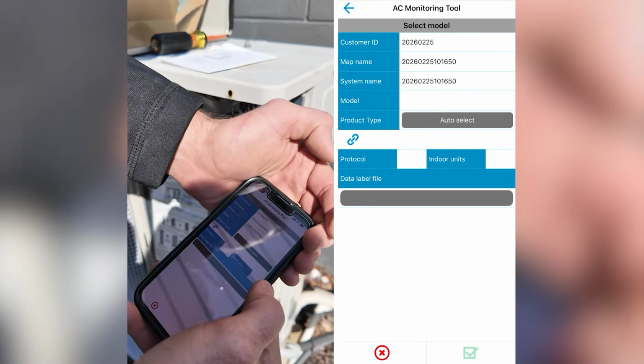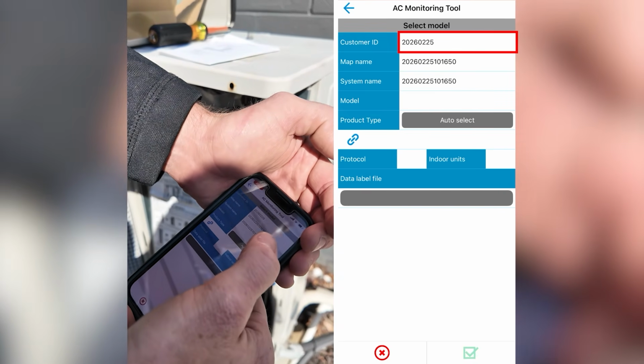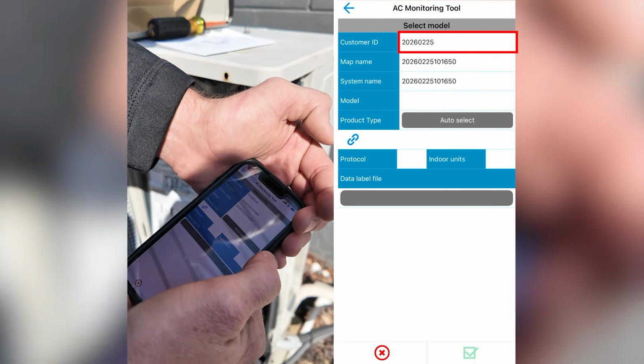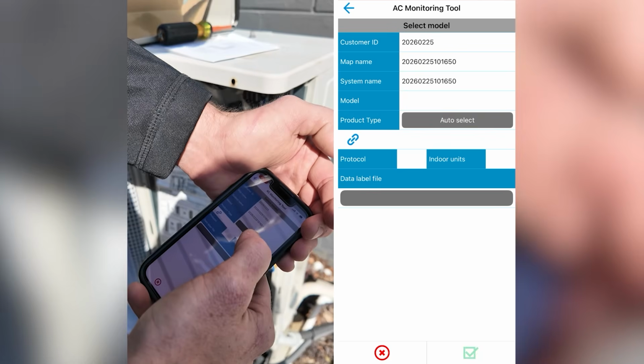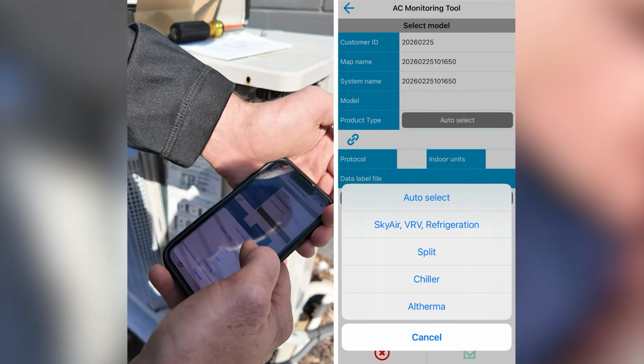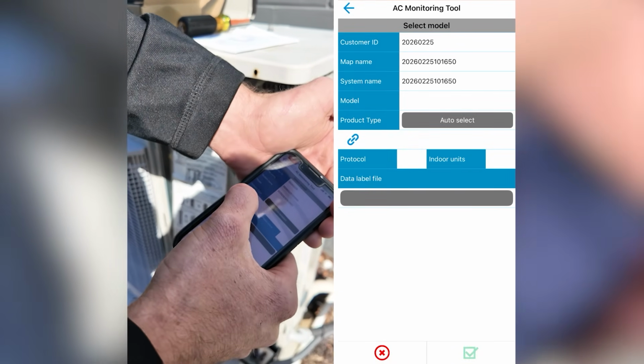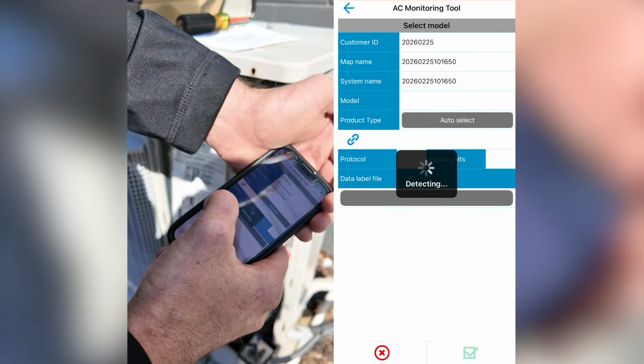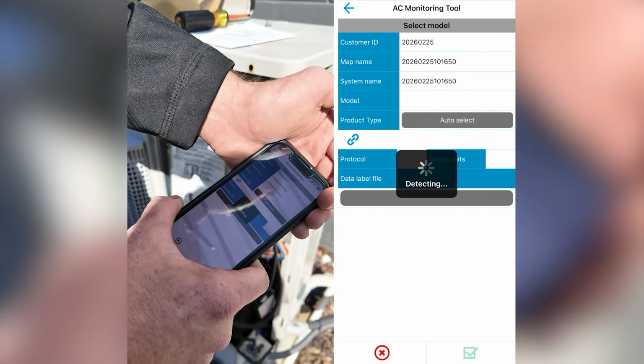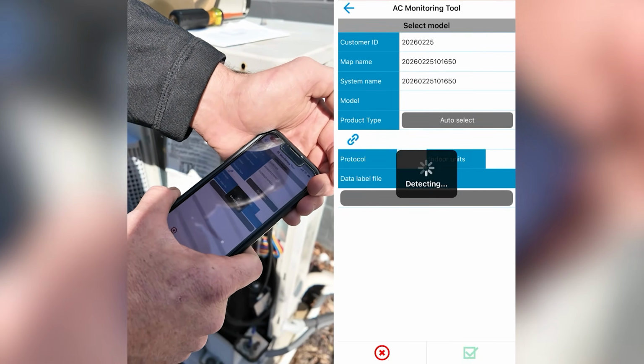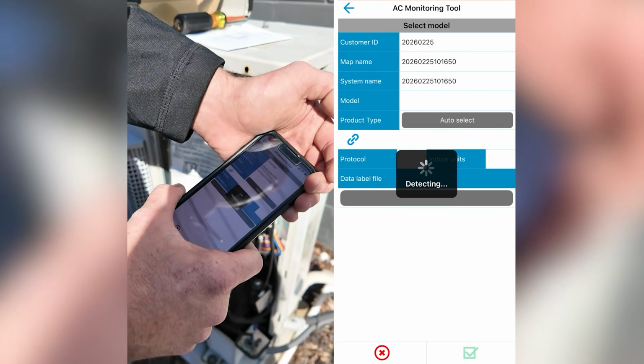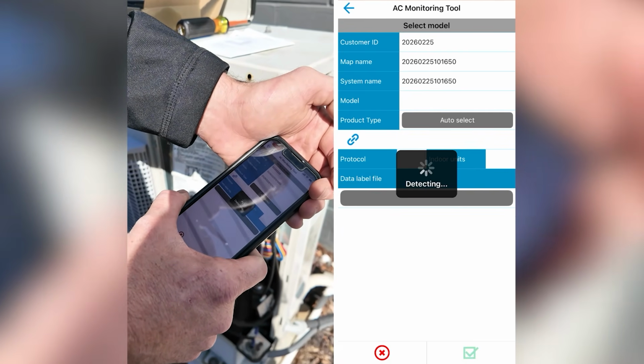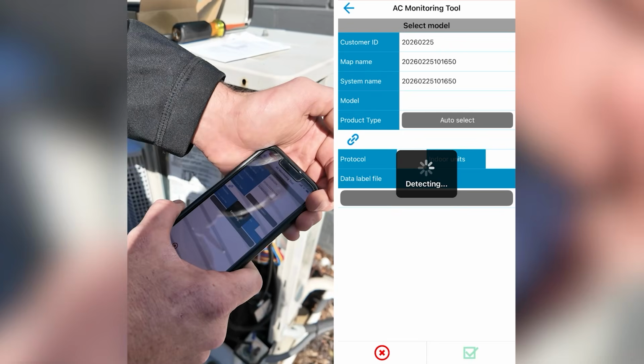Now I'm at the mapping of the system portion. It's going to give me automatic customer IDs based upon my timestamps. What I want to do now is go in here and do auto select. With auto select selected, I'm going to click the little chain link on the left-hand side and it's going to start auto detecting the piece of equipment that I have. Now remember, this doesn't select the exact model number of the equipment. It just looks at what series of equipment we might be connected to.